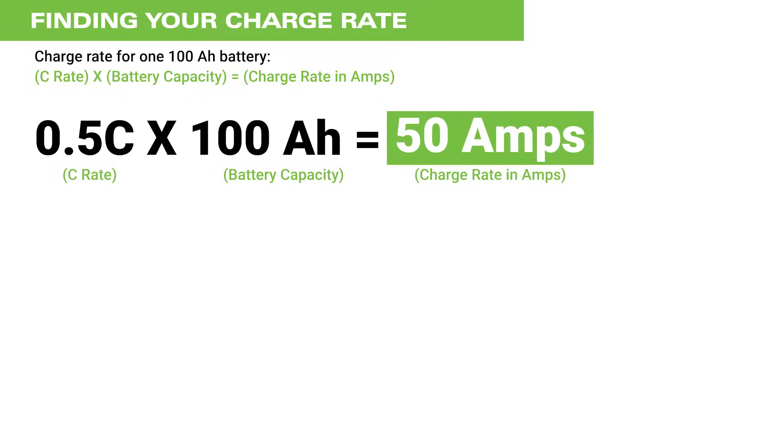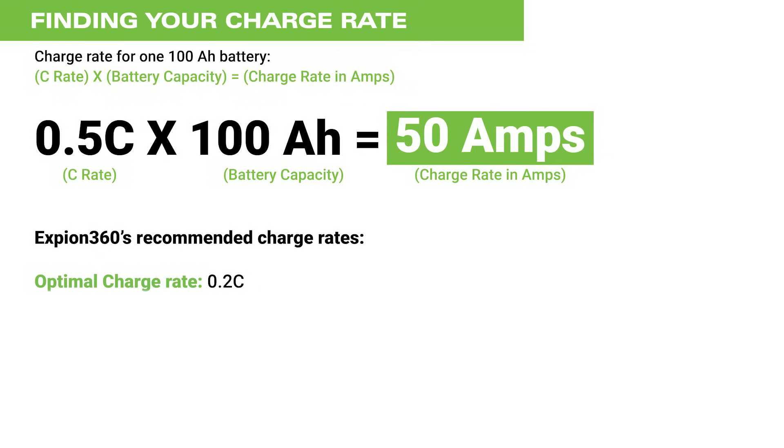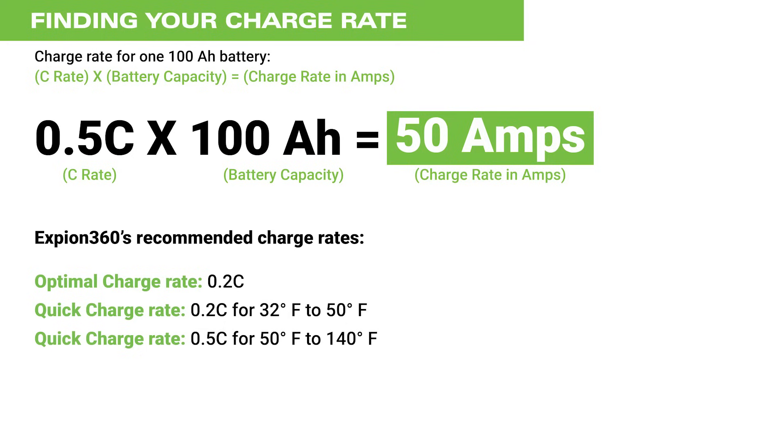Secondly, it is necessary to select an appropriate charge rate. Charge rates are expressed as ratios of C. For example, a 0.5C charge rate for a 100 amp hour battery would be 50 amps. Using Expion360's recommendations for our batteries, the following would apply using a 100 amp hour battery as an example: optimal charge rate is 0.2C or 20 amps; quick charge rate is 0.2C for 32 to 50°F or 20 amps; quick charge rate is 0.5C for 50 to 140°F or 50 amps.